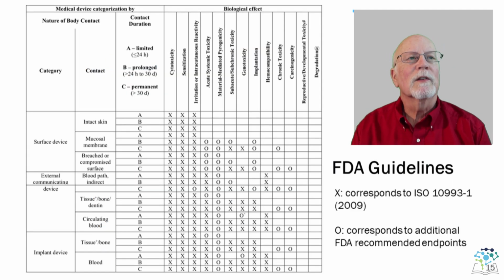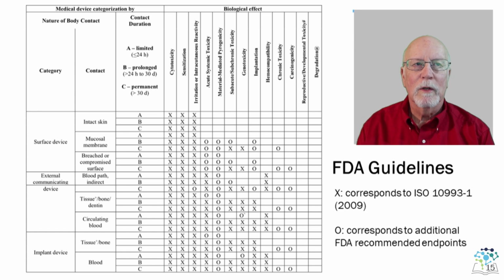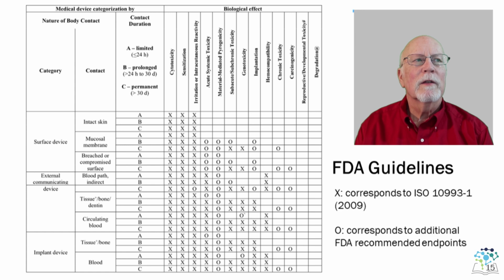Representatives from the FDA had a significant input in the development of the ISO standard table A1, but they also constructed a similar but not exact copy in their guidance document, one which is not necessarily in exact agreement with the ISO committee interpretations, but which rules in all discussions and submissions for device approval to the FDA. The differences are minimal, but are reflected in this table in the newest version of their guidance document.